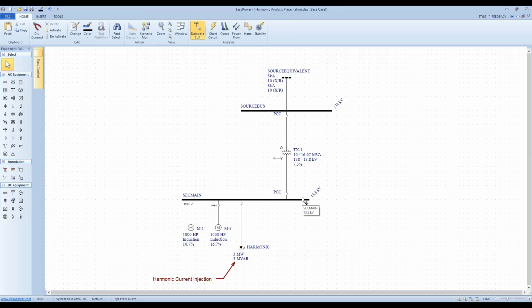Okay, 13.8. You would just take 10 MVA, or 10,000 kVA, divide by 13.8, and then divide that by 1.73. You would come out with 418 amps. That would be your 1 per unit current level. And that's true whether it's a harmonic or it's the fundamental current within the plant itself. It's 1 per unit current.